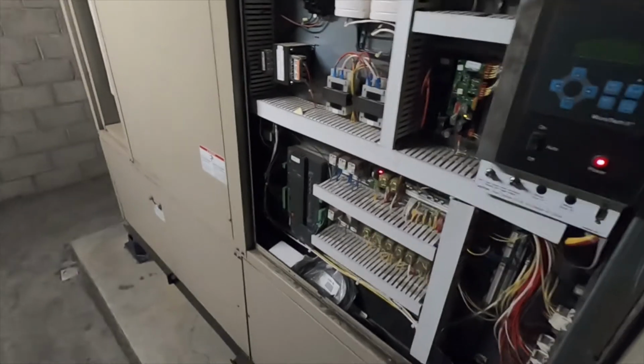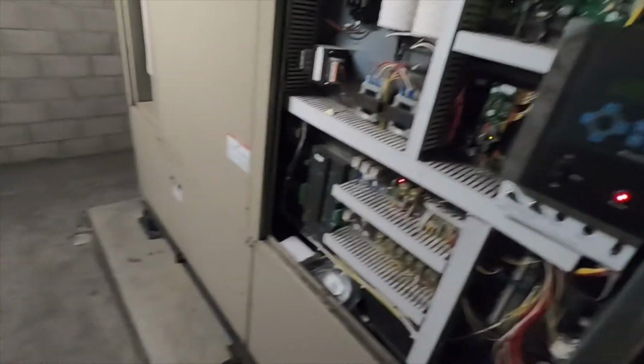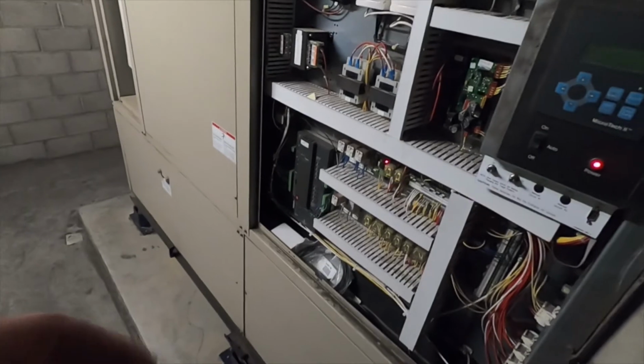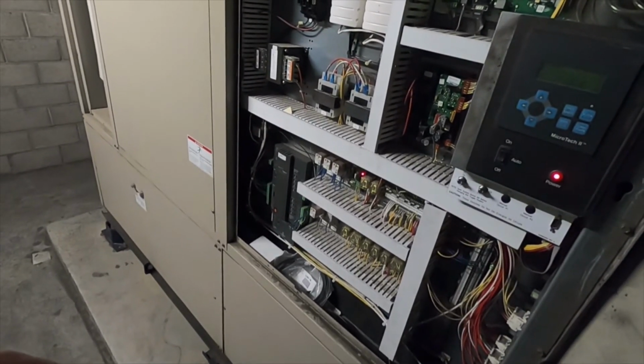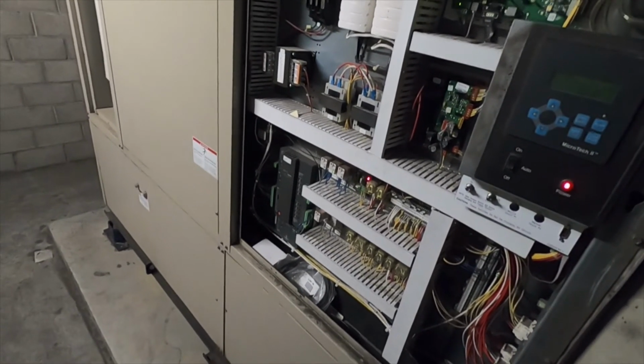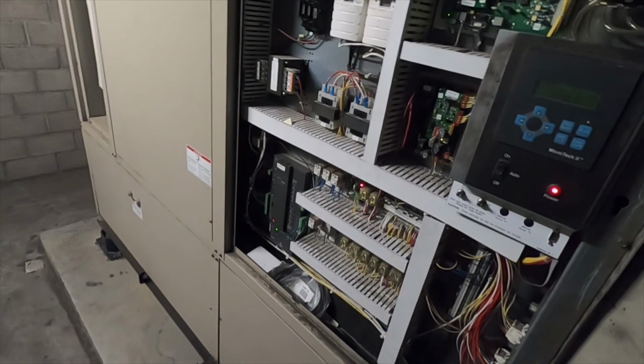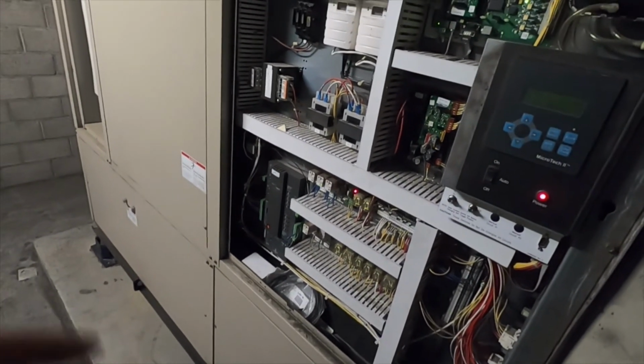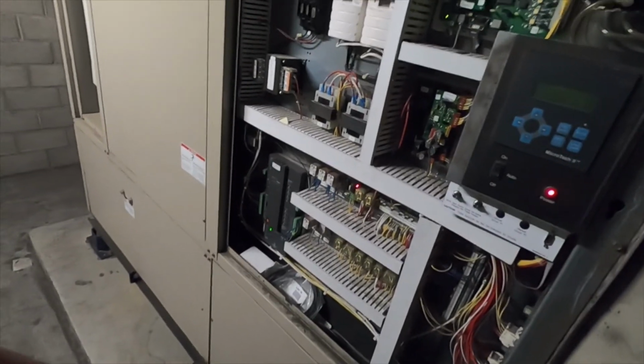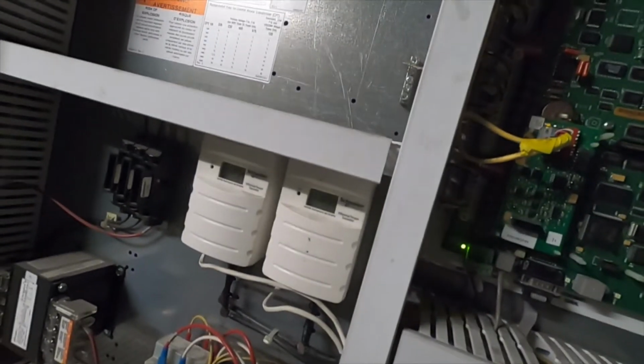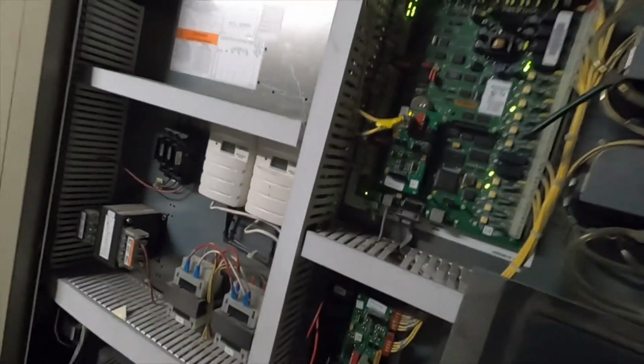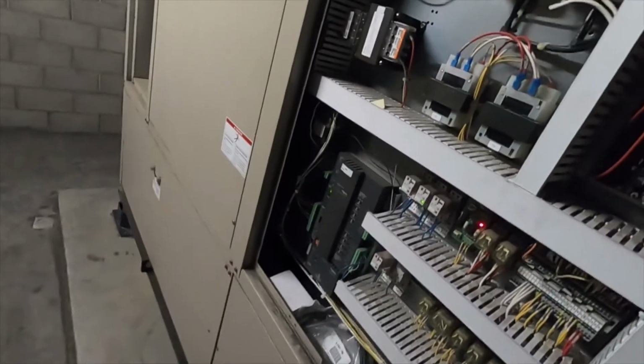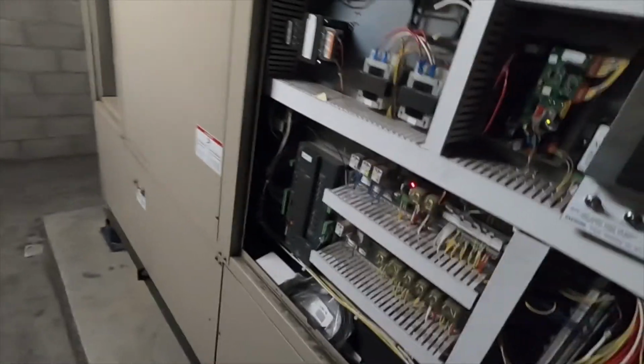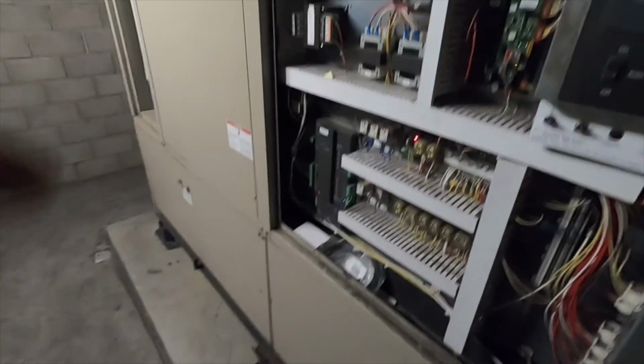But nothing too crazy, though it is control stuff. It's something that either you'll be doing or you won't be doing, adding special sensors, either supply or return. You can see we have building and duct static sensors right there. Those do not come on the unit; those were installed when this unit was first put in. And then of course the relays for enable, start stop relays, dirty filter, morning warm up, and of course enable.